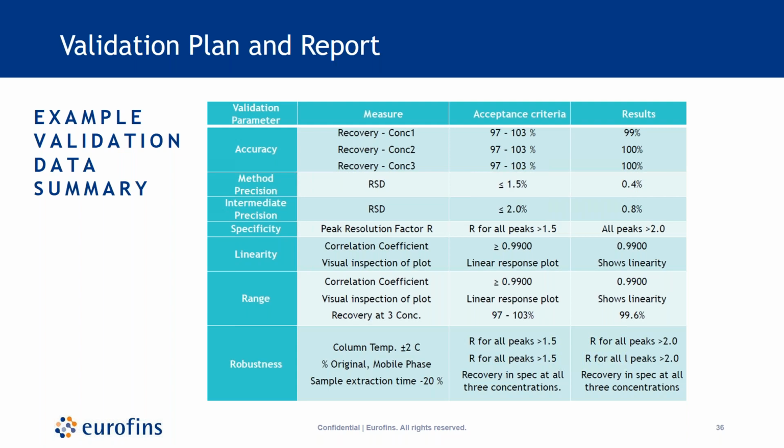This section should give us specifications for the performance characteristics that will be used. So what are the acceptance criteria for your accuracy, precision, specificity, so on and so forth. Usually it's going to be in a table format like on the screen.